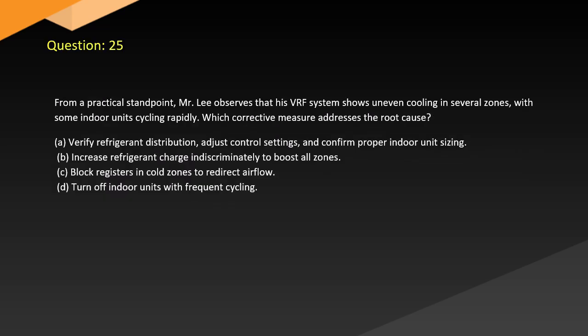Question 25. From a practical standpoint, Mr. Lee observes that his VRF system shows uneven cooling in several zones, with some indoor units cycling rapidly. Which corrective measure addresses the root cause? A. Verify refrigerant distribution, adjust control settings, and confirm proper indoor unit sizing. B. Increase refrigerant charge indiscriminately to boost all zones. C. Block registers in cold zones to redirect airflow. D. Turn off indoor units with frequent cycling.